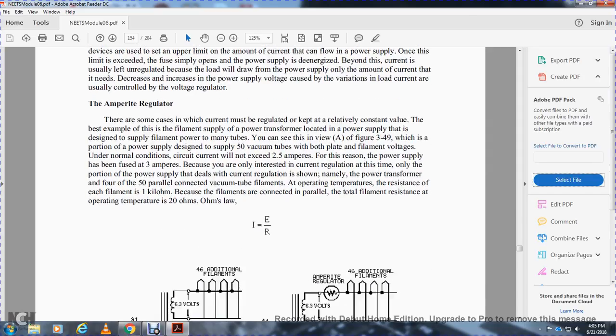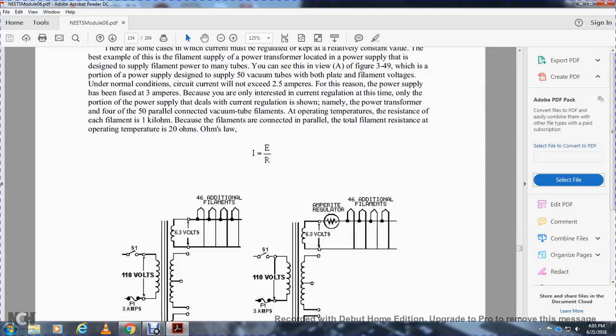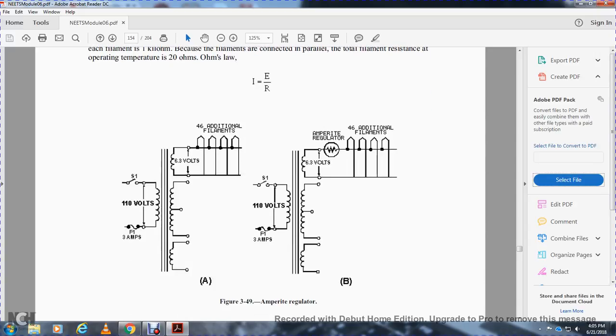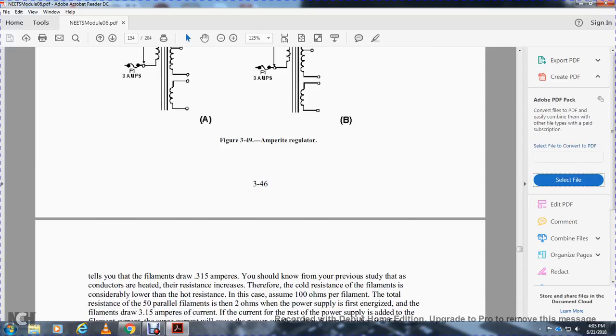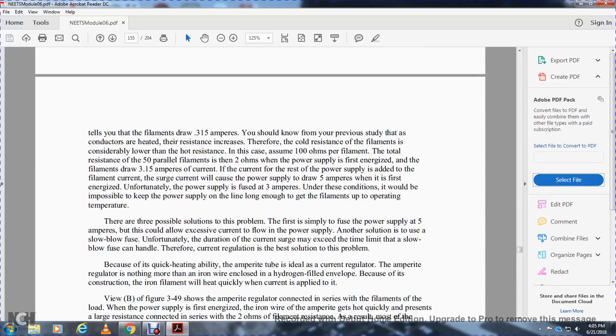at operating temperature is 20 ohms, since amps equals voltage over ohms. You can see in the figure the amperite regulator, 110 volt switch, one fuse B1, center tap, two outside filaments, 6.3 volt filaments, center tap, 110 volts, 6.3 amp regulated, 46 additional filaments. This tells you the filaments draw .315 amps. That you should know.